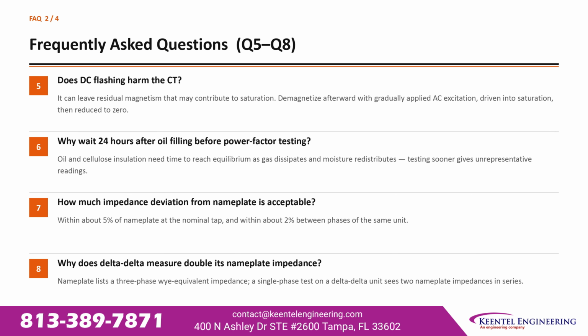Does DC flashing harm the CT? It can leave residual magnetism that may contribute to saturation. Demagnetize afterward with gradually applied AC excitation driven into saturation, then reduced to 0.